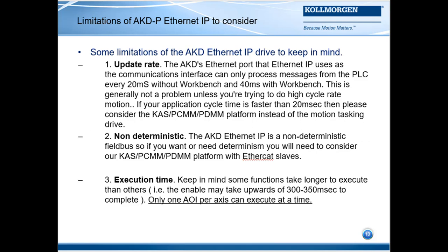Non-deterministic. The AKD Ethernet IP is a non-deterministic fieldbus. So if you want or need determinism, you will need to consider our KAS PCMM PDMM platform or other EtherCAT controllers and the use of the AKD EtherCAT drives as slaves.